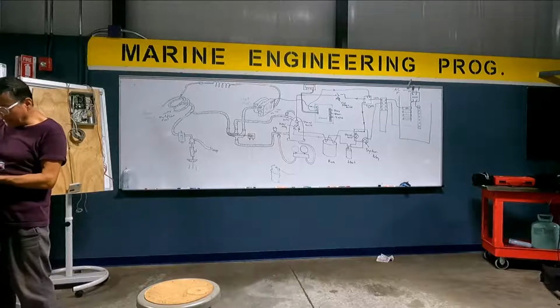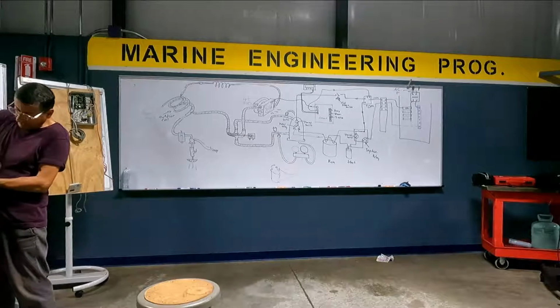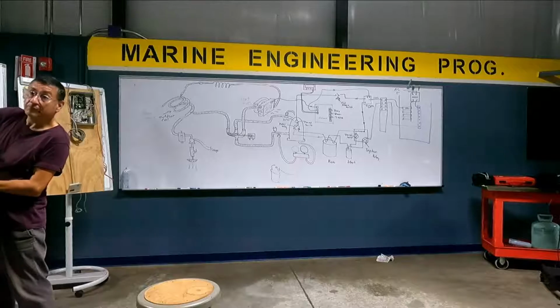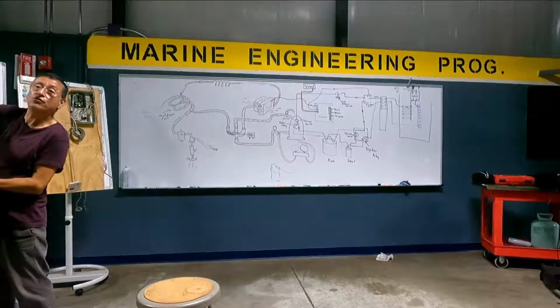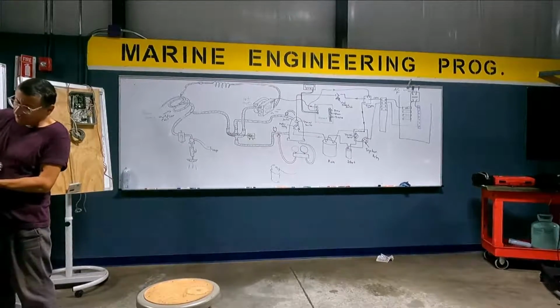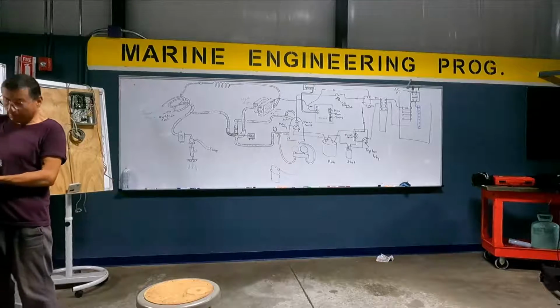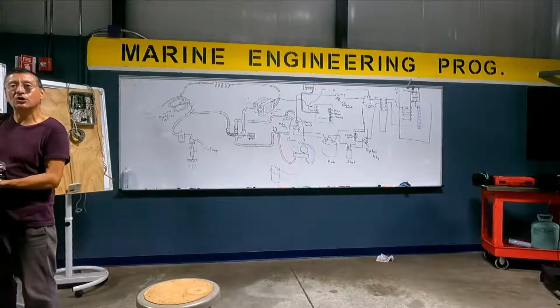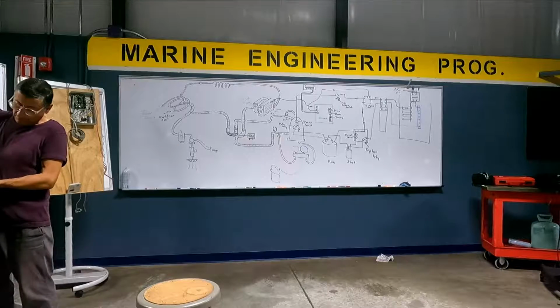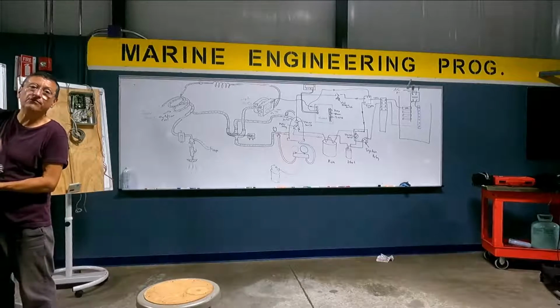Normally, in the circuit boards, they have 3 fuses here. You need to verify those fuses. One of the fuses controls the blower, another controls the raw water pump, and the other controls the Y valve. You check the fuses or replace the fuses.